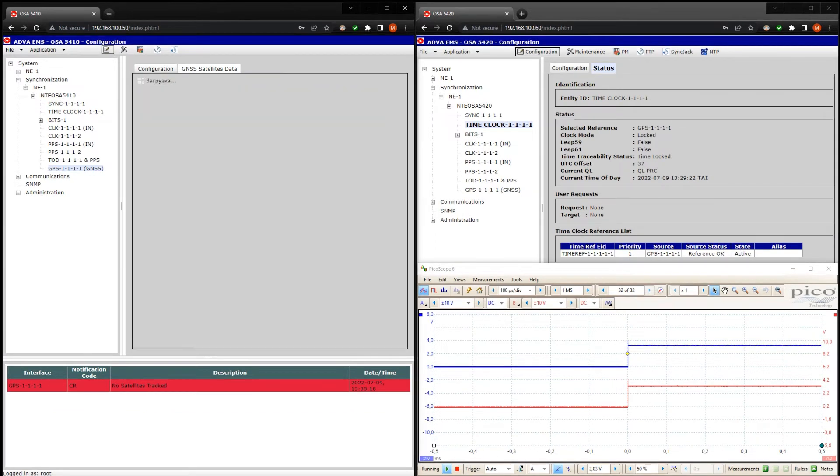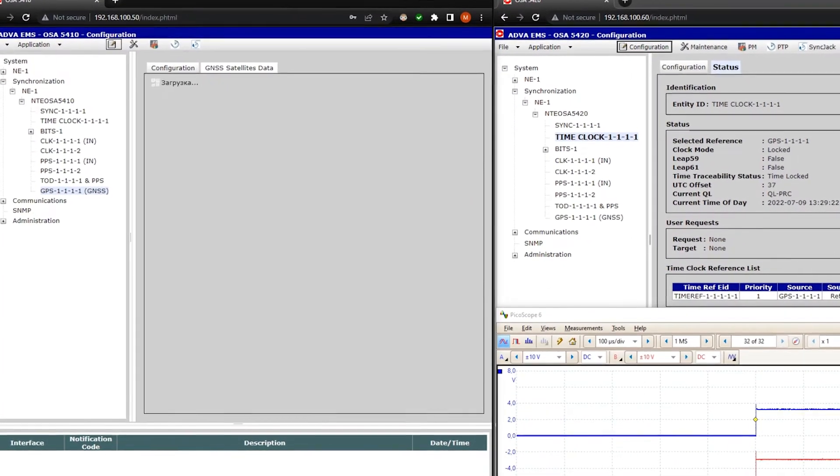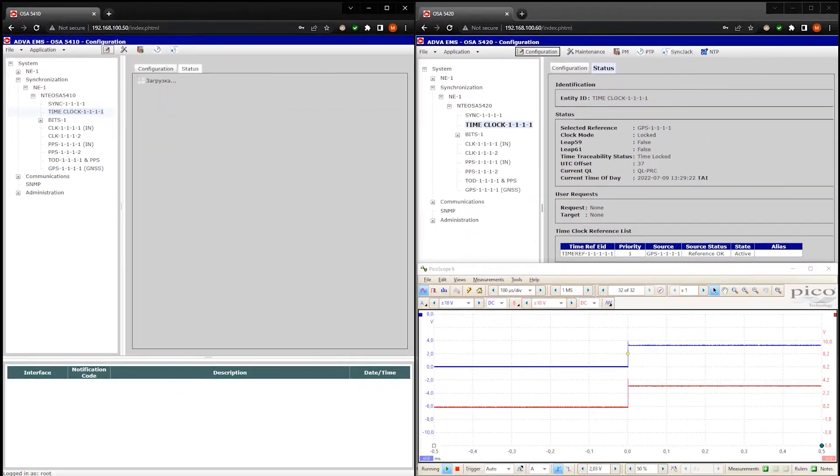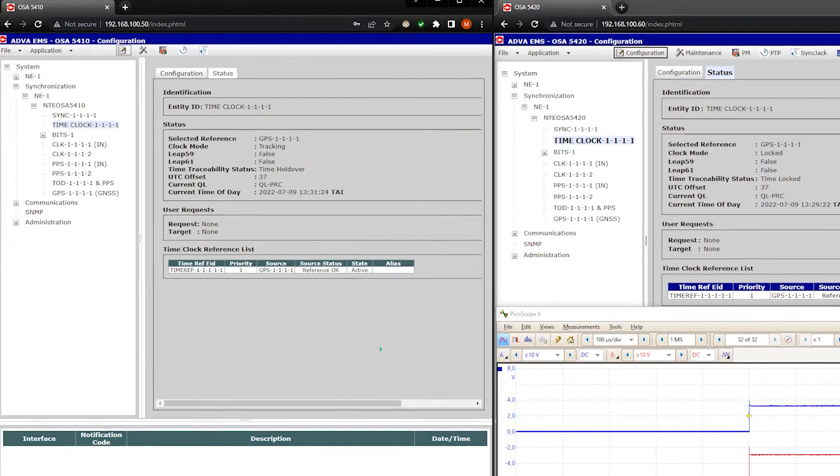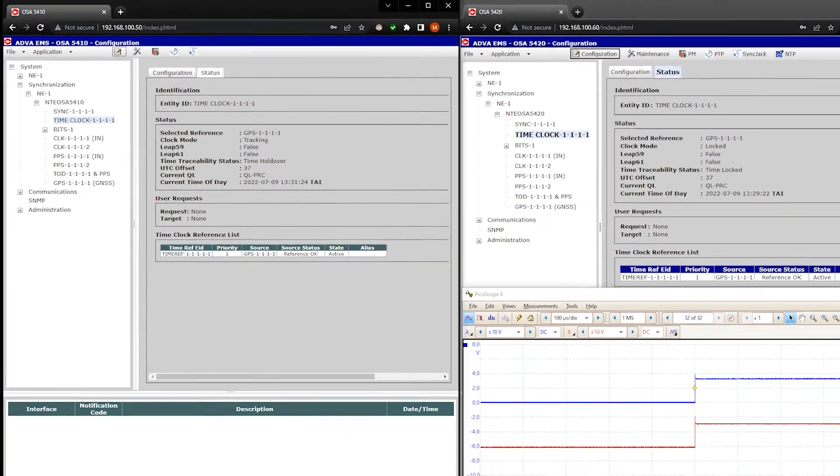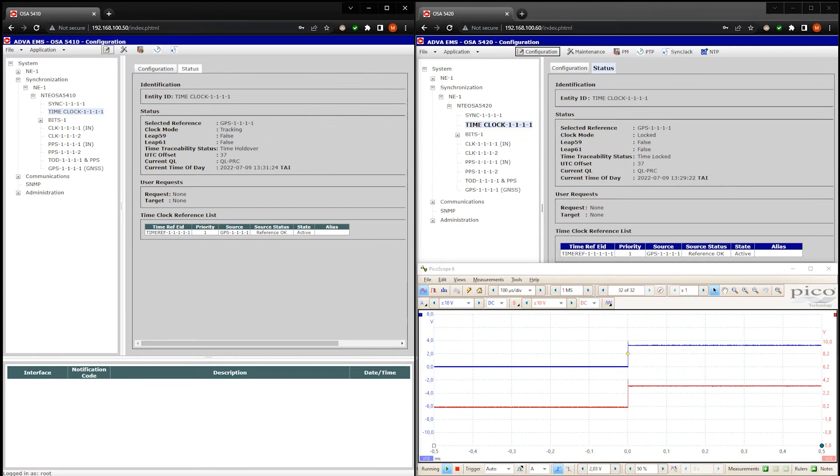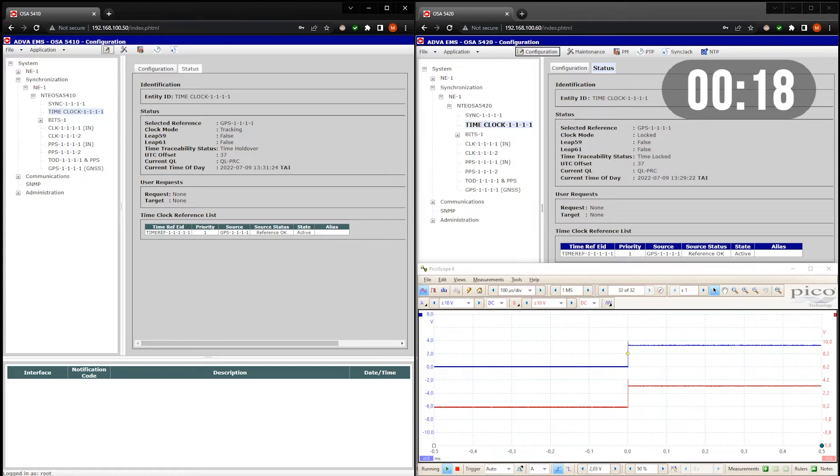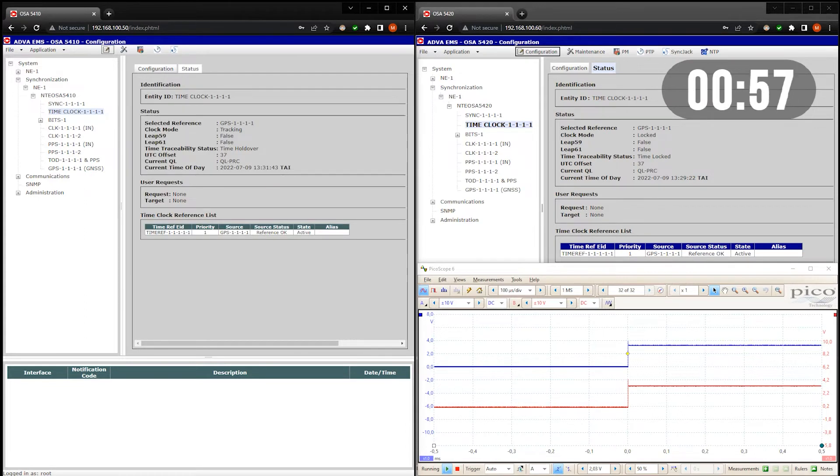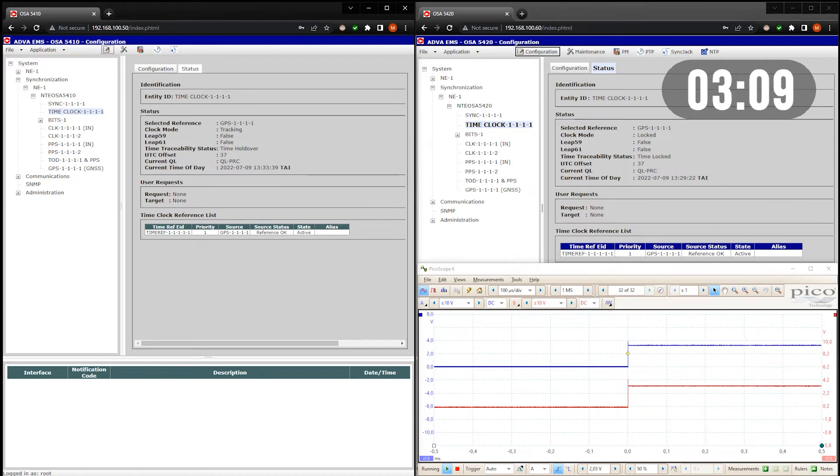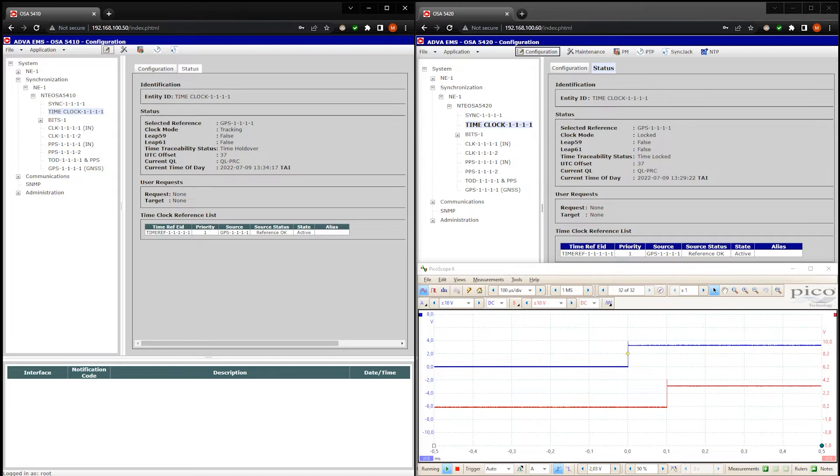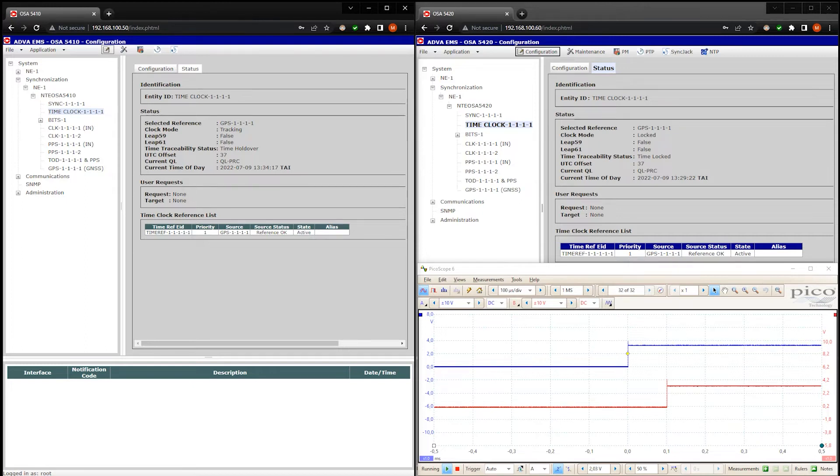However, this time the embedded GNSS receiver quickly switched to our fake signals. Let's go to the time clock menu. GPS clock is active and accepted by the time server. It's in the tracking mode. And I think we will see the PPS phase jump in a couple of minutes. Speeding up our video. It took 4 minutes to adjust the internal clock to our fake signal. And exactly for the predefined 100 microseconds.